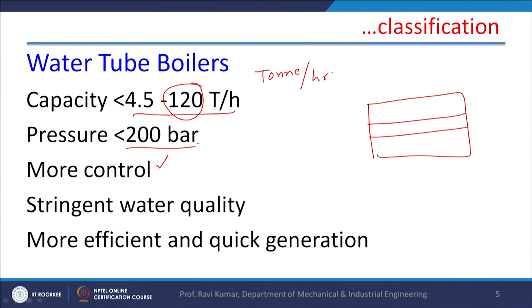If there are fluctuations in demand we normally go for fire tube boilers, but in water tube boilers more controls and greater safety are required, and stringent water quality has to be maintained because water is flowing inside the tube. If any scaling takes place inside the tube or water is contaminated with mud, it will grossly hamper heat transfer. Water tube boilers are more efficient and steam generation is quick. Some water tube boilers are once-through boilers — water enters from one side and steam exits from the other, so there are no drums in those boilers.